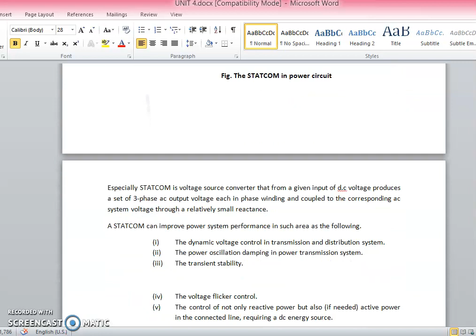A STATCOM can improve power system performance in such areas as the following: the dynamic control in transmission and distribution systems, the power oscillation damping in power transmission systems, the transient stability, the voltage flicker control, and the control of not only reactive power but also active power in the connected line, requiring a DC energy source.